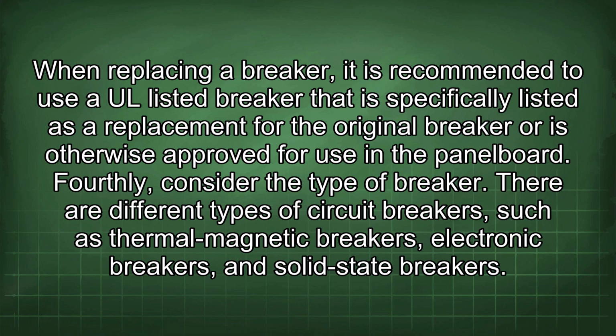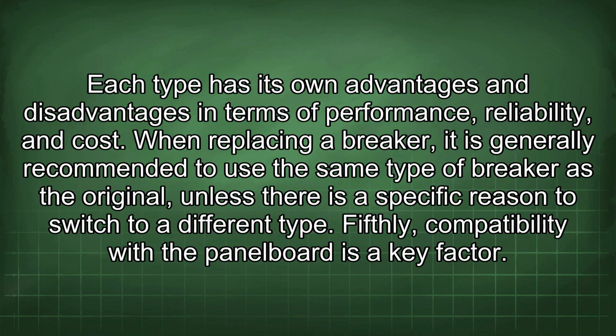Fourthly, consider the type of breaker. There are different types of circuit breakers, such as thermomagnetic breakers, electronic breakers, and solid-state breakers. Each type has its own advantages and disadvantages in terms of performance, reliability, and cost. When replacing a breaker, it is generally recommended to use the same type of breaker as the original unless there is a specific reason to switch to a different type.